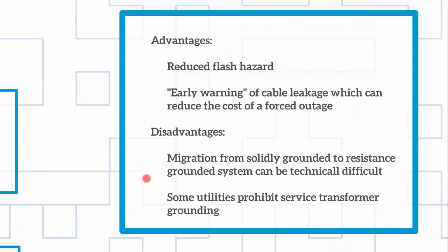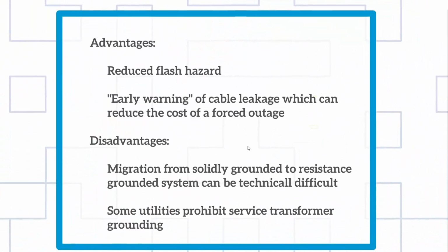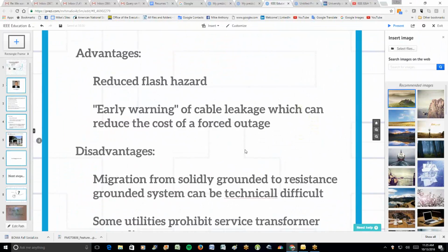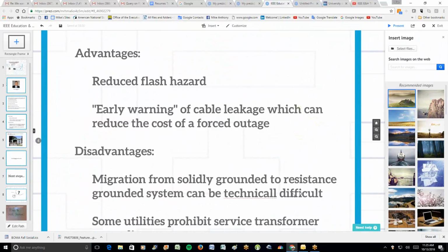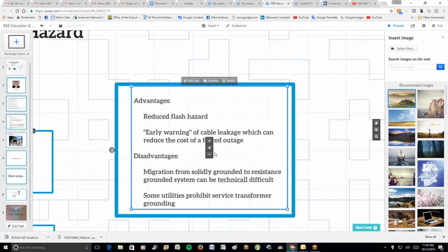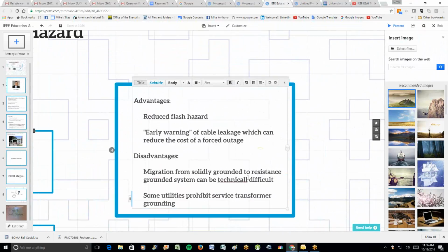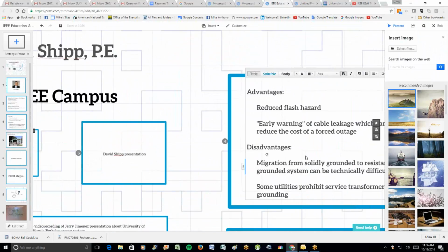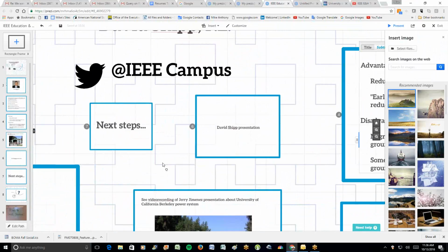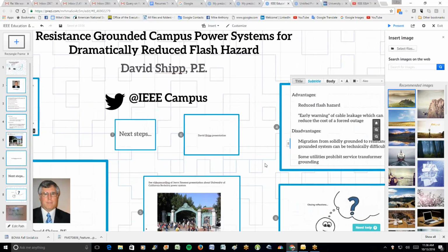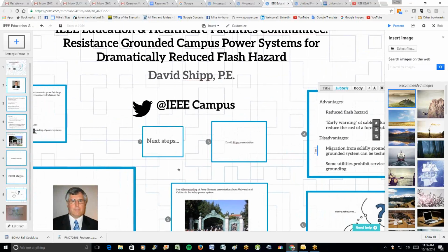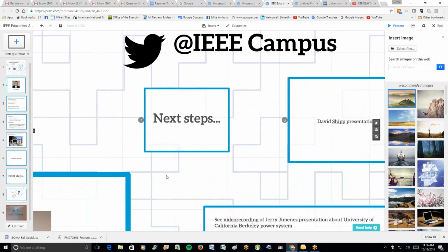You have to have some special training for the maintenance people, but it's 2 to 4 hours and you're done. It's not hard, but remember, if I've got high resistance grounding and I get a ground fault, you're going to go to 480 volts line to ground, not 277 or 0. So you're not going to have many amps flow or much incident energy, but you're going to have a lot higher voltage than normal. Now it's within range that you can handle and control it, but the guy's got to know it's going to be 480, not 0 or very low. And so he's got to be able to handle the safety part of it.